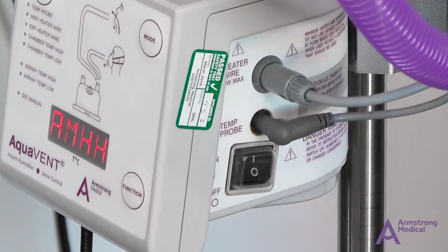Non-invasive mode is indicated by the icon with the face mask. Invasive mode delivers a target gas temperature at the end of the breathing circuit of 40 degrees. Non-invasive mode delivers a target gas temperature at the end of the breathing circuit of 34 degrees. High flow and CPAP are both non-invasive therapies. Select the non-invasive icon. To select the mode, press the mode button at the top right of the screen.